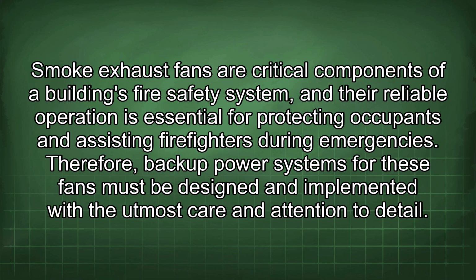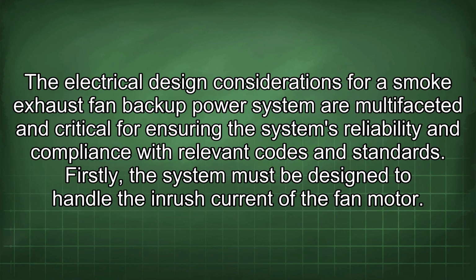Smoke exhaust fans are critical components of a building's fire safety system, and their reliable operation is essential for protecting occupants and assisting firefighters during emergencies. Therefore, backup power systems for these fans must be designed and implemented with the utmost care and attention to detail. The electrical design considerations for a smoke exhaust fan backup power system are multifaceted and critical for ensuring the system's reliability and compliance with relevant codes and standards.